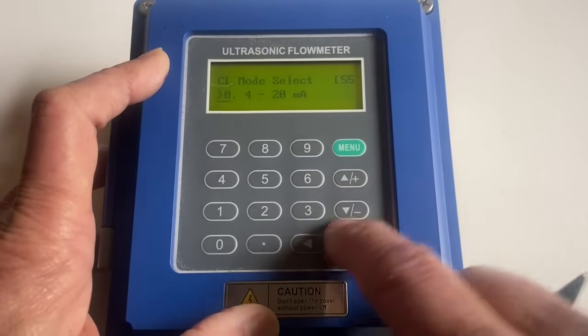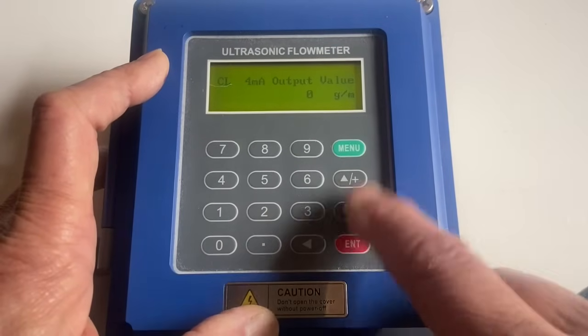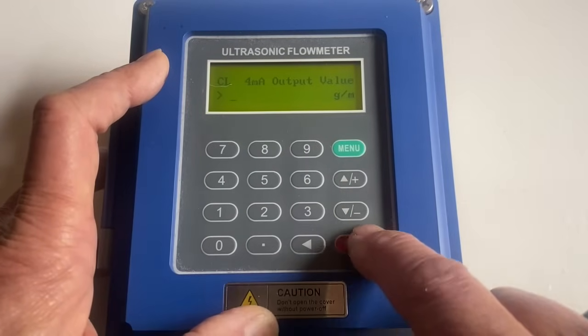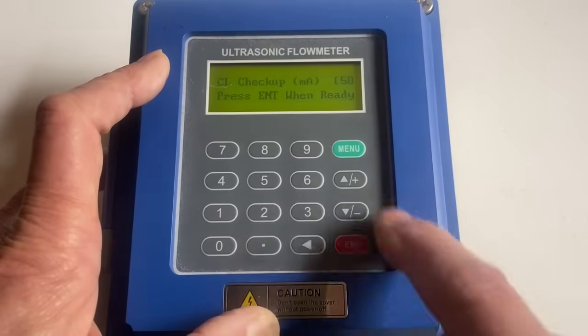Enter. We're going to mostly be 4 to 20 milliamps. The 4 milliamps corresponds to zero gallons per minute and the 20 milliamps corresponds to 230 gallons per minute. So these are all the correct values.